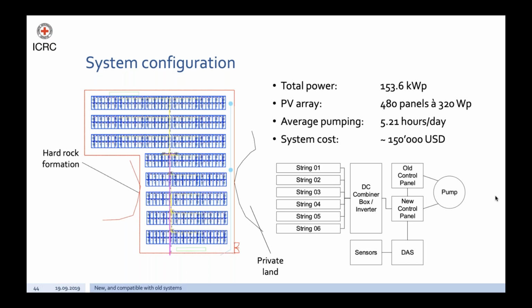The system is optimized at an inclination of the panels of 15 degrees. In January, for example, this allows production of around 9,000 kilowatt hours compared with 10,000 kilowatt hours that would be possible at an inclination of 30 degrees. However, in order to avoid shading, a larger and therefore more expensive structure would be required. It was also taken into consideration that water consumption is higher in summer than in winter, and therefore we considered 15 degrees appropriate. It allows the pumps to run for 5.21 hours per day on average.